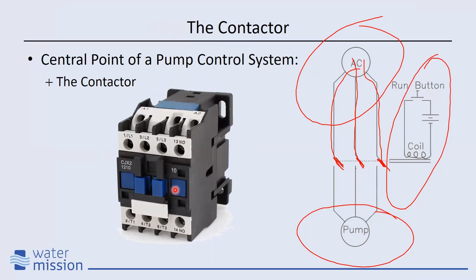Let me go back quite a number of slides here real quick. I want to take a look at this contactor again. A characteristic feature of this contactor is that right in the center is almost always going to be a different plastic insert that's able to move. So the best way to identify a contactor is by looking for that.